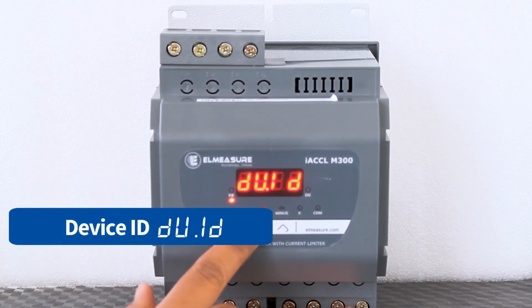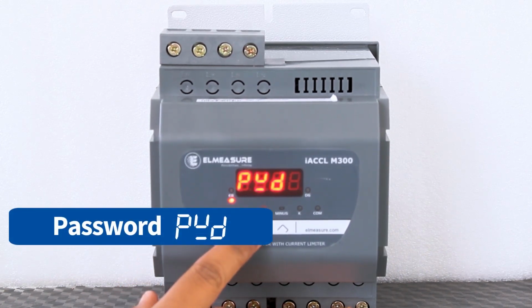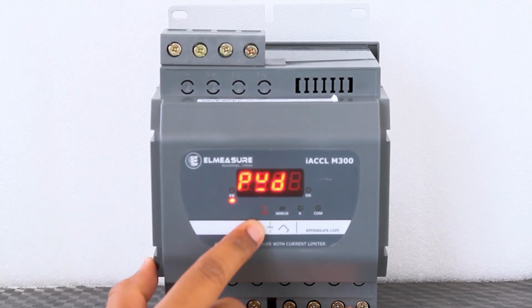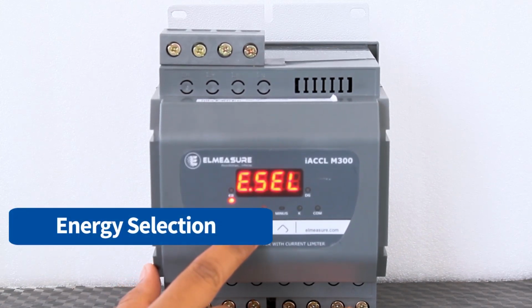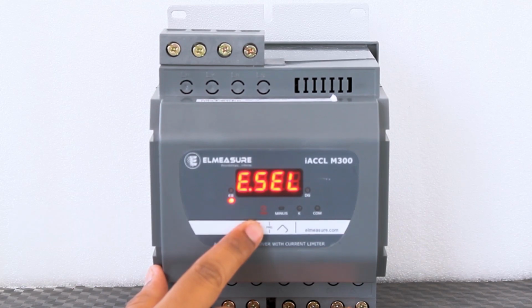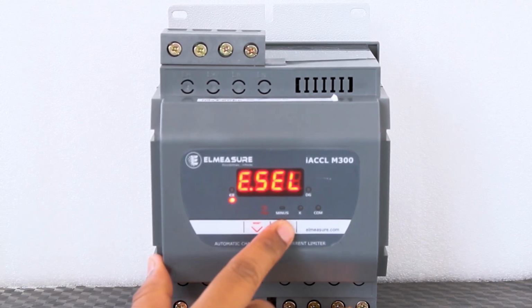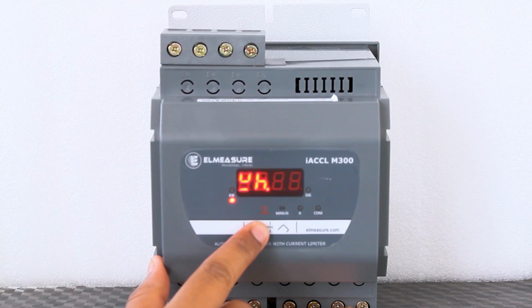This is parity. This is device ID. The device ID can be set from 1 to 247. This is password. If you want to change the default password, you can change it here. This is energy selection, WH, VAh. By default it will be WH. You can change the values here.